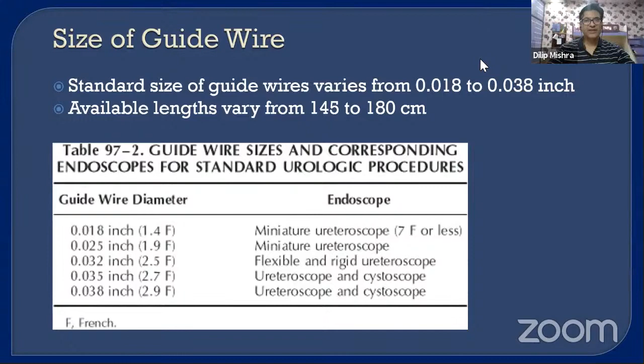And here is the list of scopes through which these guide wires can be used. Generally, guide wires are 145 to 180 centimeter in length. The tip design is very much important because the tip needs to be floppy and it needs to be flexible. Either it could be straight, angled, or J-tipped according to the preference of the surgeon. And it needs to be floppy because once you're inserting inside the pelvicalyceal system, it should not injure the mucosa of the pelvicalyceal system.